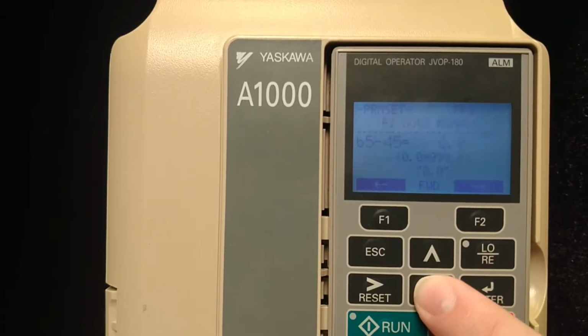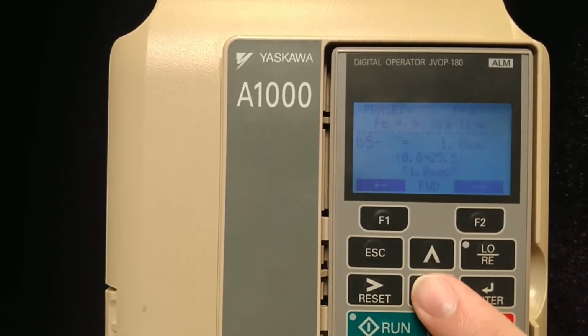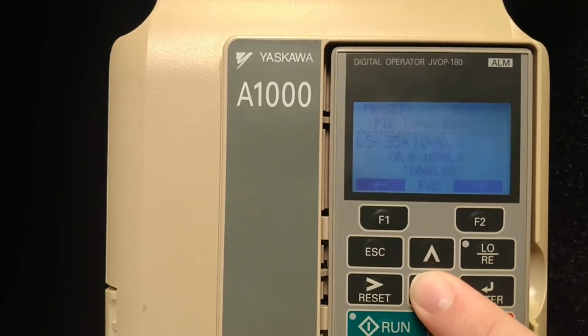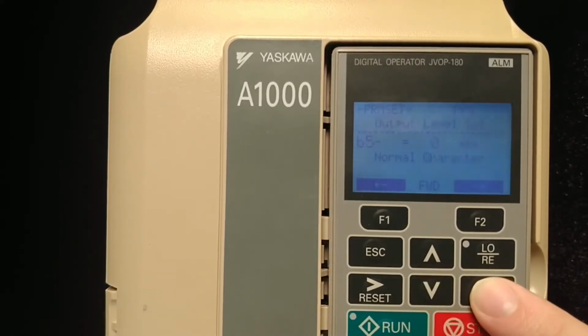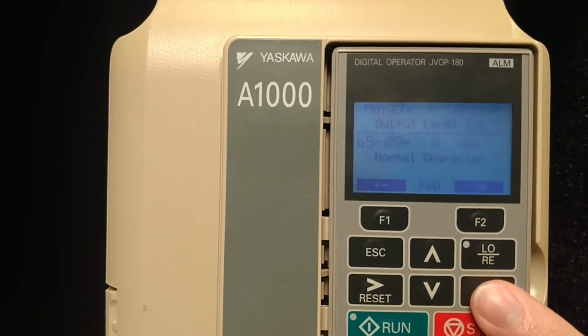The next parameter we'll want to set is our PI output level selection, either to be direct acting or reverse acting. This parameter is B509. Direct acting would be filling a tank. Reverse acting would be removing water or whatever from a tank.